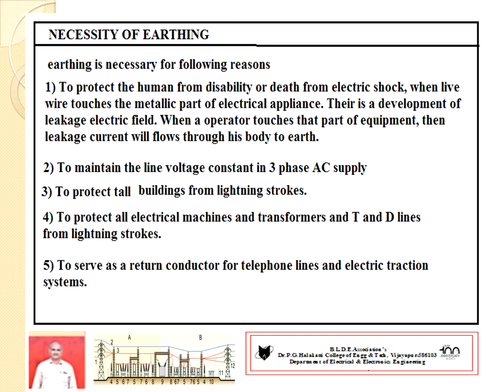What is the necessity of earthing? It is already known. Number one, to protect human life from disability or even death from electric shock. When the live wire touches the metallic part of the body, a leakage field develops. In industry, when an operator touches that part of the equipment, the leakage current will flow through the body. You remember, to protect the human body from electric shock, number one. Number two, to maintain the line voltage constant in three-phase AC supply, the neutral wire, the star point, should always be earthed. Then to protect historical buildings, like the Taj Mahal, Gol Gumbaz, and other monuments from lightning strokes, it is also important.